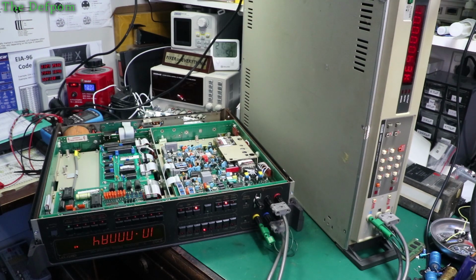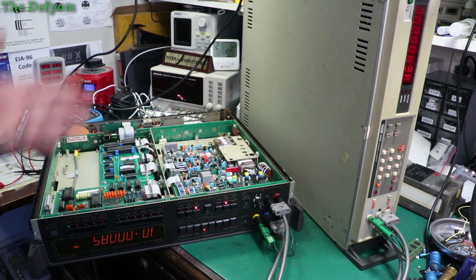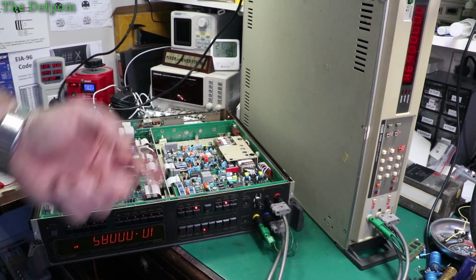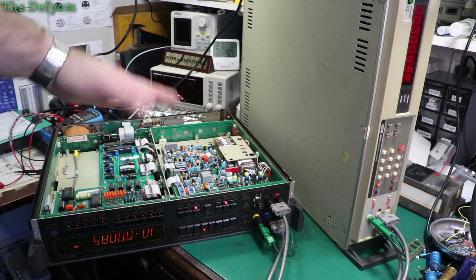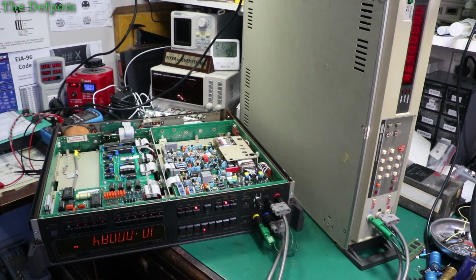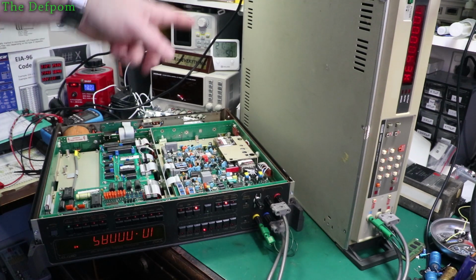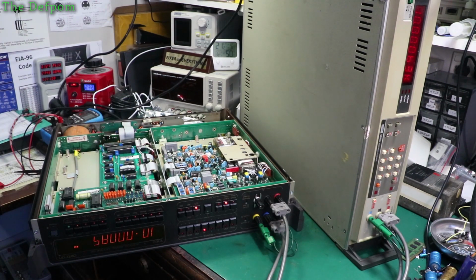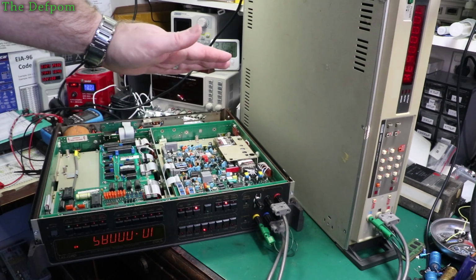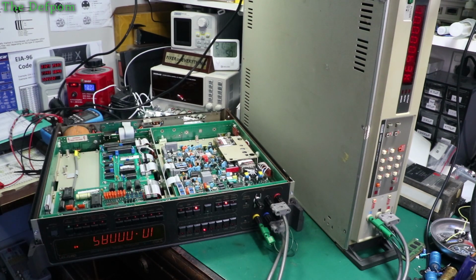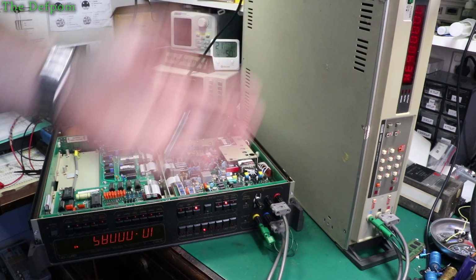Let's turn the filter on, get the next digit. Yeah, that's okay. It's out by 20 counts or something, but considering the covers are off and it's not warmed up properly, that's not surprising. The temperature's a bit low as well, at 21 degrees. It should be slightly warmer than that, but not much. It seems to be working. So why is it giving a self-test error? That's the weird bit, because it starts on that range measuring a 10k resistor. That's going to require some more investigation, I think.